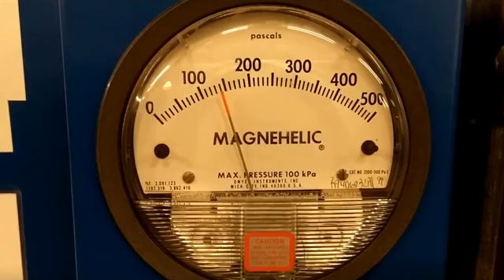So that pressure difference, which you can see here, is around 145 pascals, and that means the bags are fairly dirty. So probably around 200, maybe 250 pascals, the bags will need to be replaced. But you should speak to your manufacturer to find out what the pressure difference should be across the filters in your AHU, as they do vary.